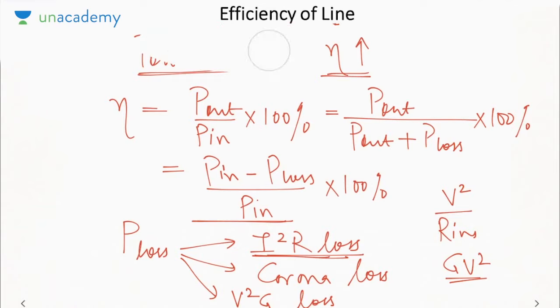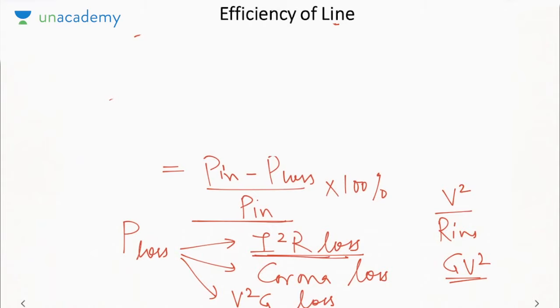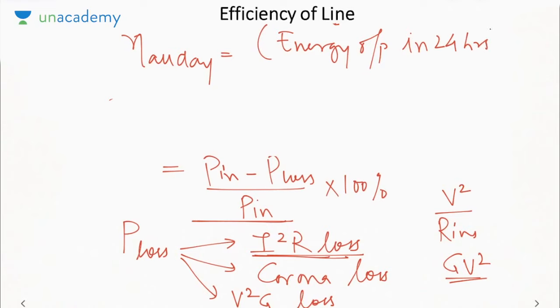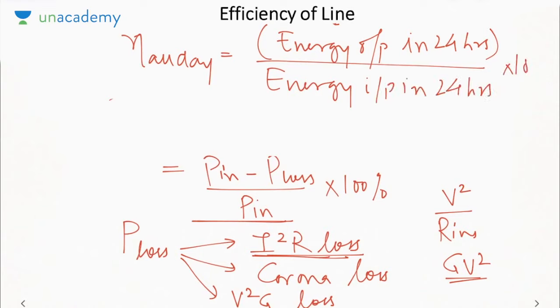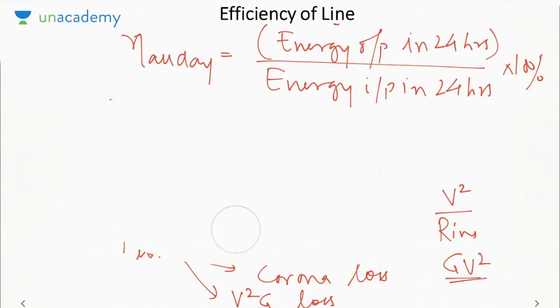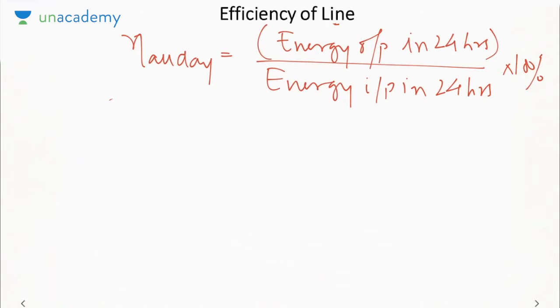Similarly, we define all-day efficiency for some systems, like for the case of a distribution transformer, eta all day is energy output in 24 hours by energy input in 24 hours. So that is your all day efficiency, but we will not define it for the case of a transmission line. We will only define the normal efficiency, that is output by input. In case of a transmission line, the output is taken at the receiving end and input is applied at the sending end. So efficiency will be simply receiving end power by sending end power into 100%.